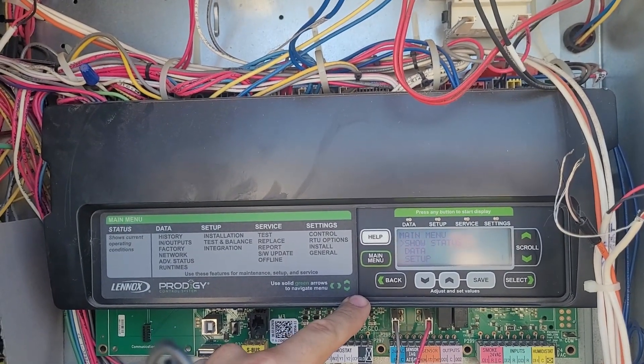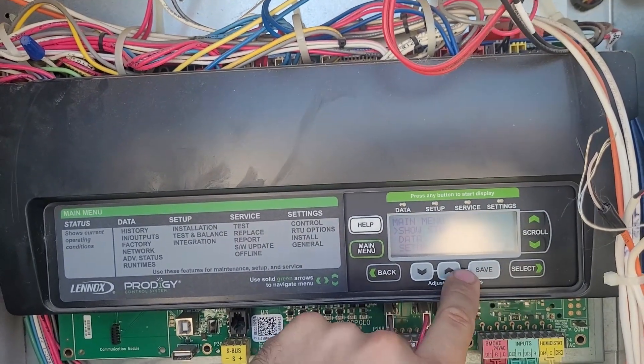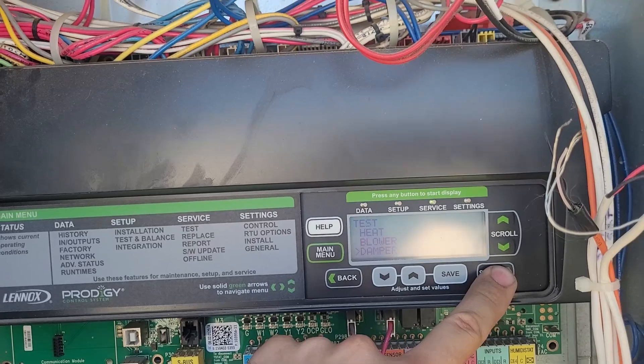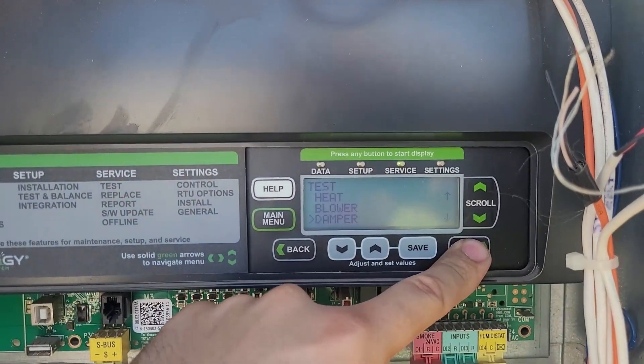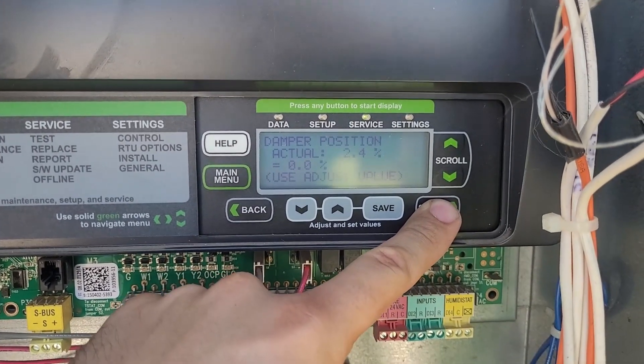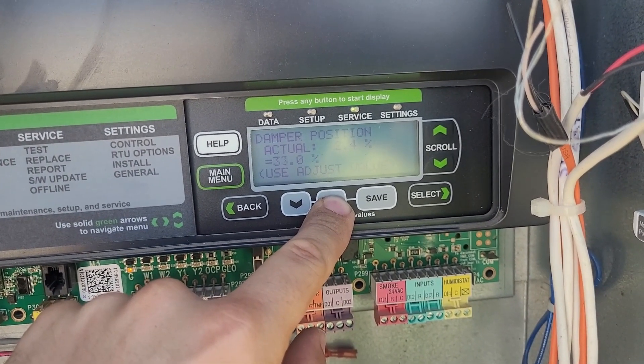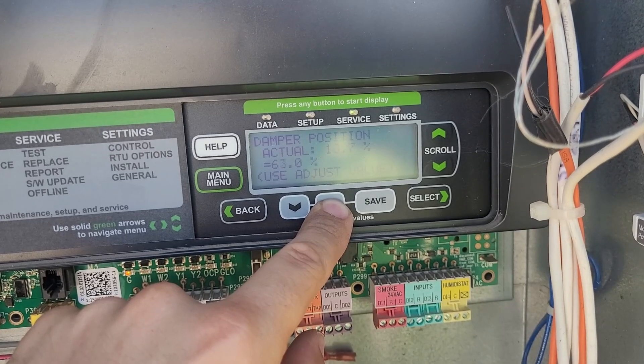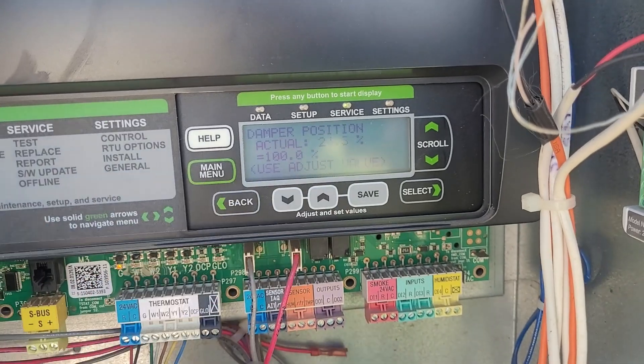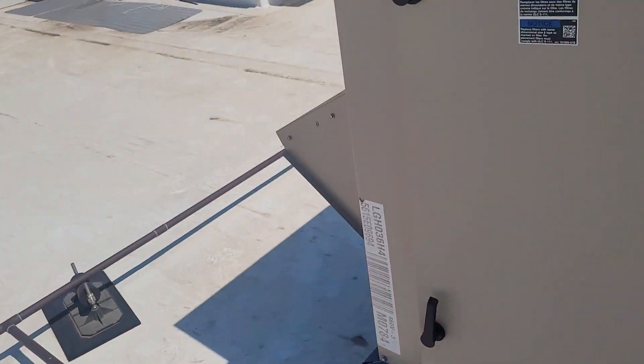If you want to test the function of your economizer damper, go to Main Menu, then Service, then Test, then Damper. Go to damper position and you can begin to adjust it there. You can run it all the way up and it gives you damper feedback as well. I'm going to run this all the way up to 100% and the feedback appears that it's working, but I'm going to go ahead and verify that it's actually moving.